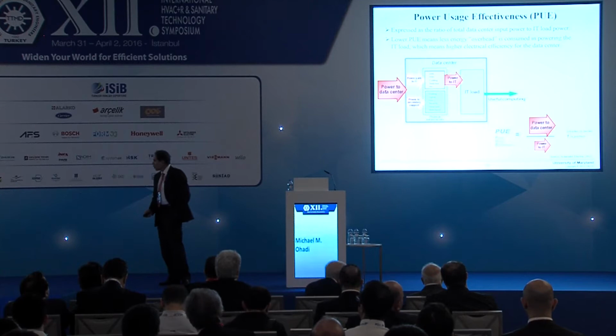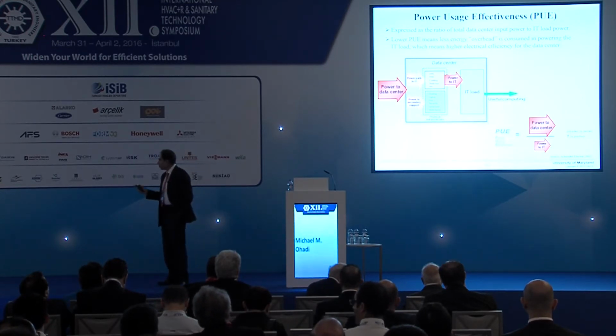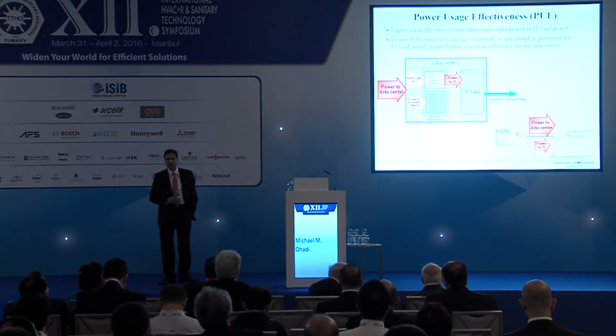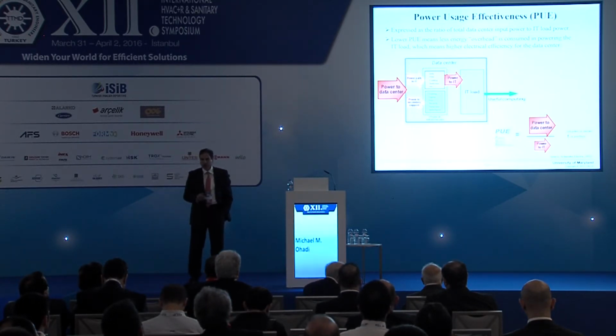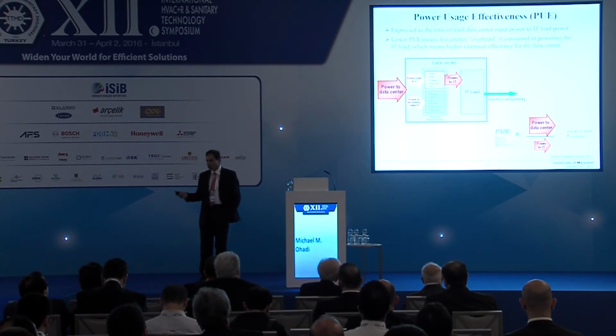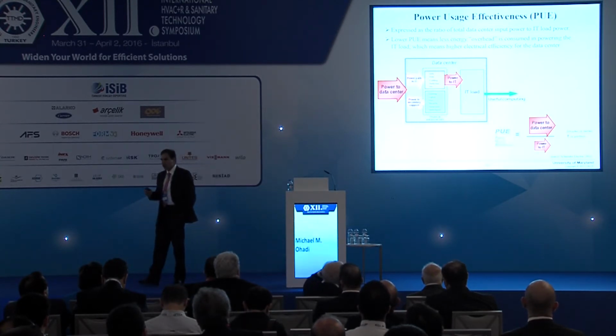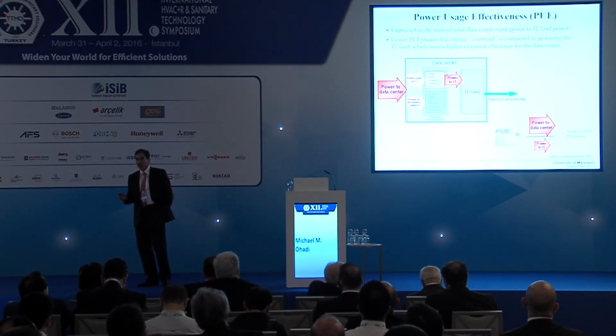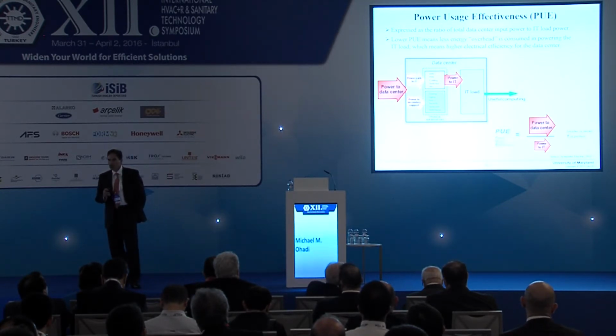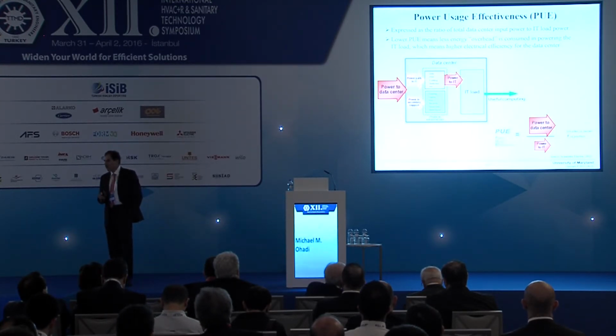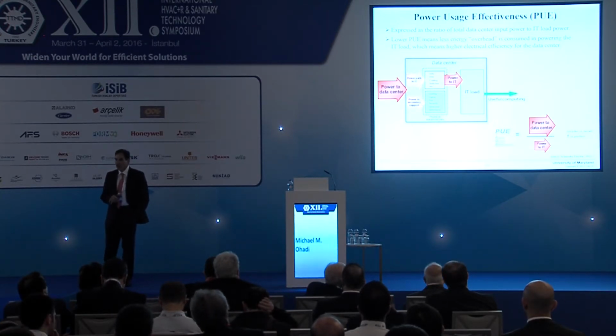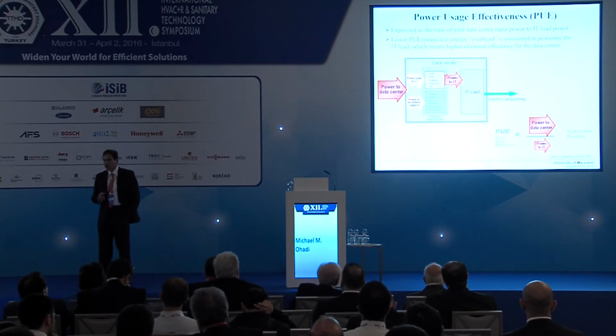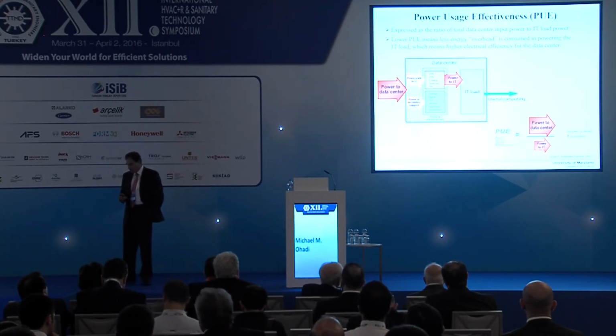We call that power utilization efficiency, PUE: power to the data center over power to IT. A perfect data center would have PUE equal to 1, meaning you bring all the total power to the IT devices and use nothing for cooling. That would be great, but the second law of thermodynamics cannot be violated, so we will never have a situation where PUE equals 1. But we could get close to 1, and I'll show you some numbers.